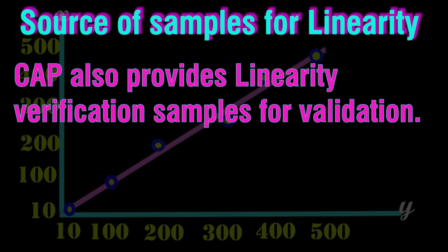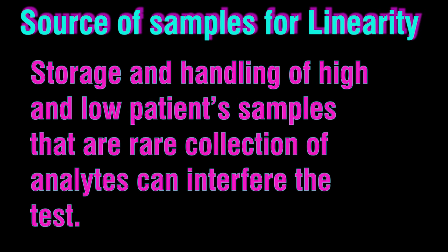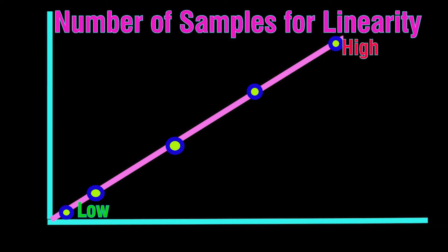The CAP Instrumentation Resource Committee offers linearity surveys as a tool for evaluating linearity. The linearity program provides pre-prepared analyte-spiked human samples, mostly serum or some urine samples, covering the full expected operating range for the analytes being tested. Lyophilized samples were used earlier, and the analyte-spiked individual samples minimize the imprecision due to manual pipetting.